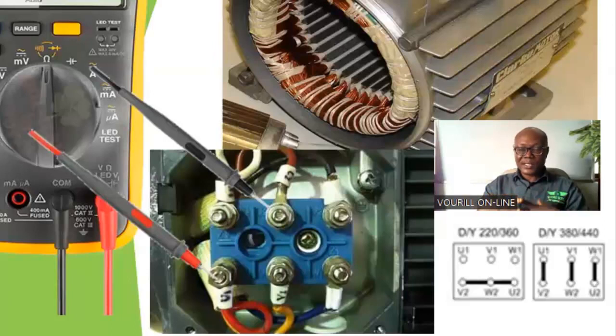When you carry out resistance tests, you will use a different meter, not this one now. The milliohms meter. We have another training on electrical measurement and testing. You can check that training out, where we discuss how to use the megohm meter, the milliohms meter, the hipot testers, and tests like the insulation resistance test, the dielectric absorption ratio test, the polarization index test, and others. They are discussed in that particular training. So you can check that training out.